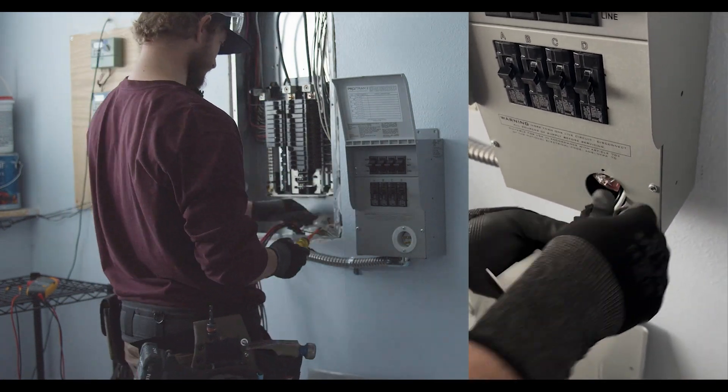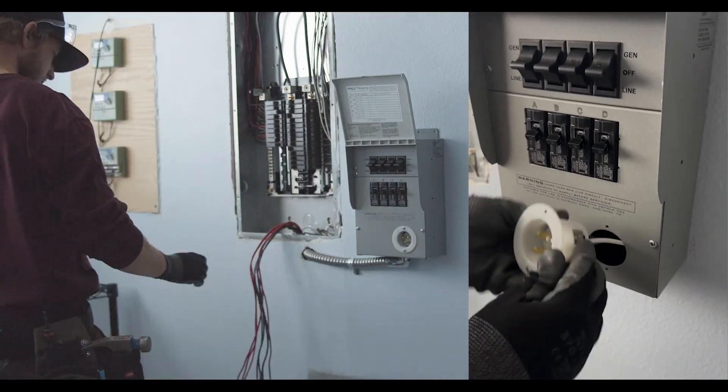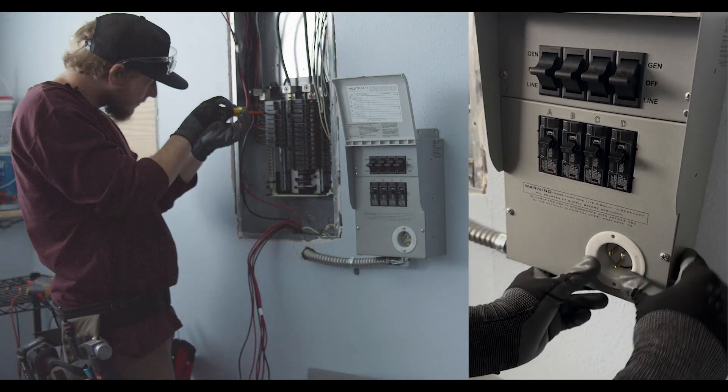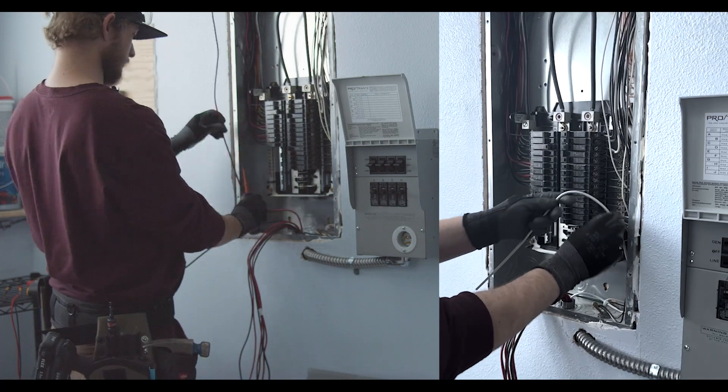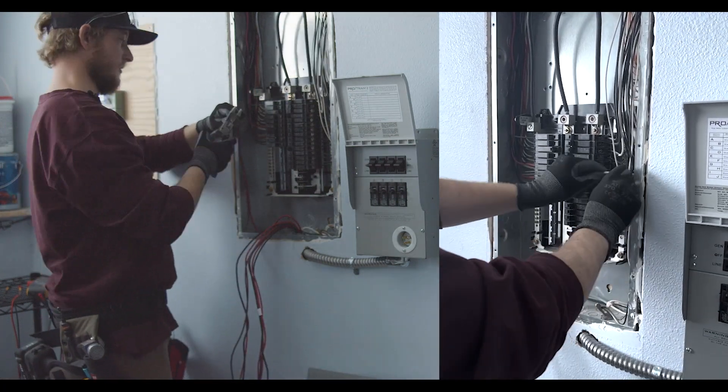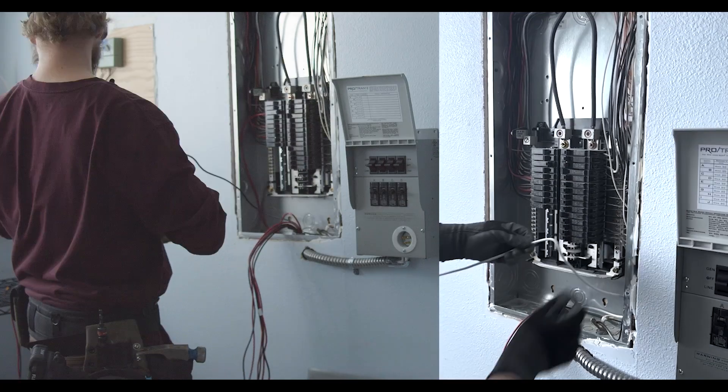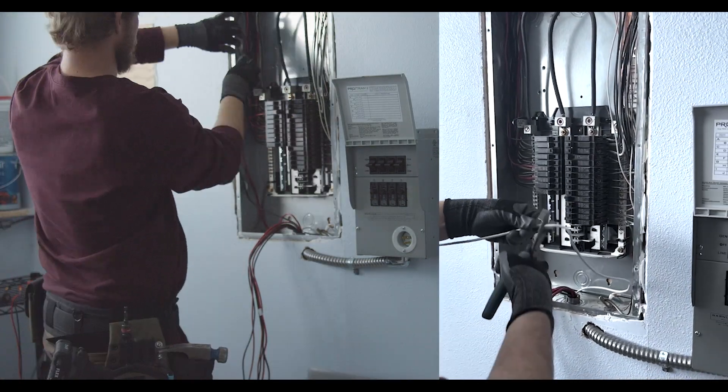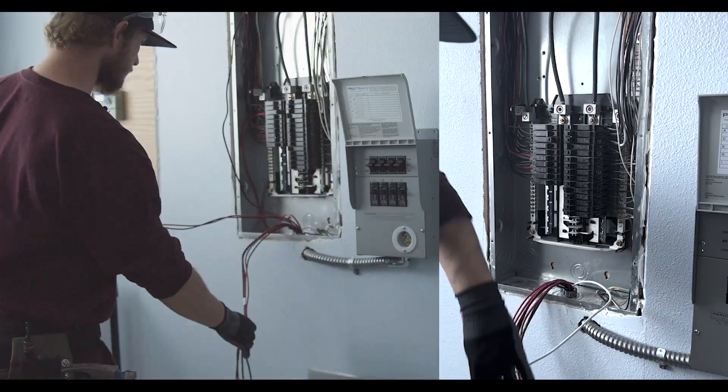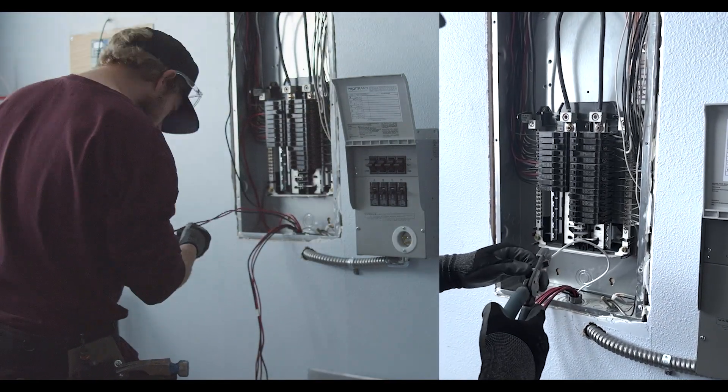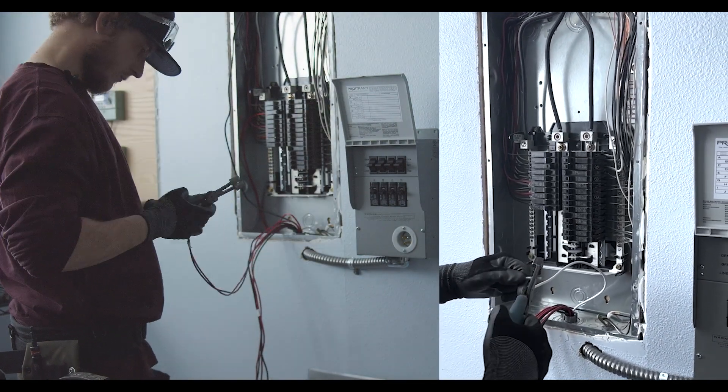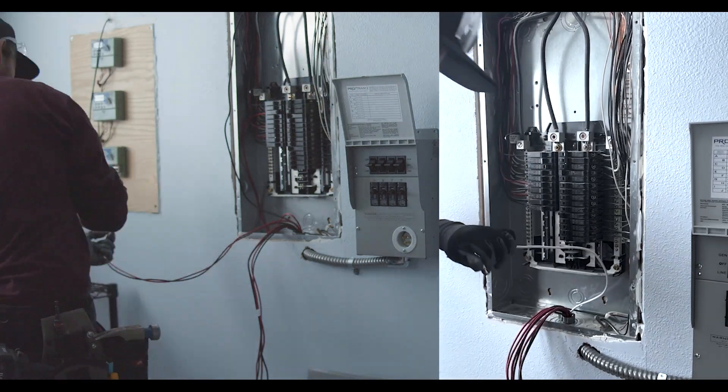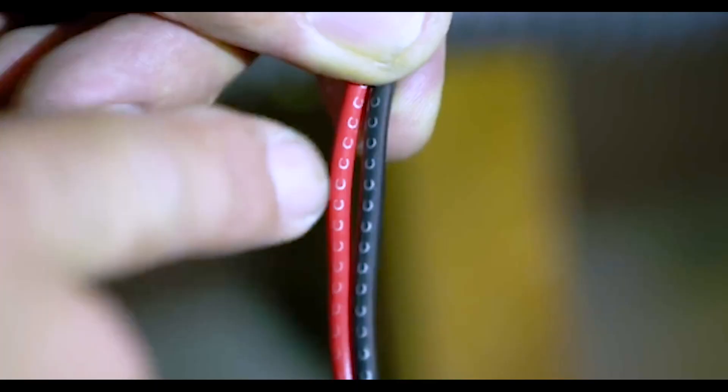On the sub panel side you will have a neutral wire which is white, a ground wire which is green, and then you'll have eight other wires. Four are red and four are black. You want to tie in the ground wire with the other ground wires on the ground bar in your sub panel. You want to tie in the neutral wire with your other neutrals on the neutral bar.